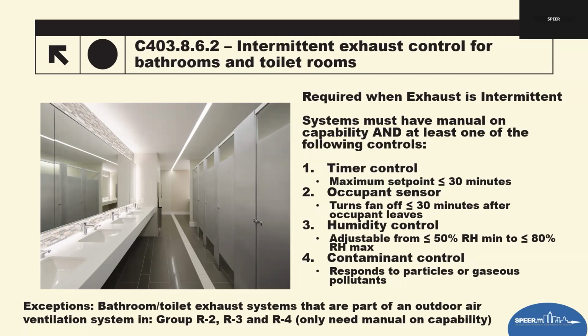And then if you have contaminant-based controls, these controls activate the fan in response to air quality triggers such as VOCs, parts per million, particles, CO2. The code now allows these systems to have alternate ways of basically ensuring proper ventilation when the space is occupied. There are exceptions, so are occupancy integrated systems. There's one important exception. So if the bath or toilet exhaust is part of the outdoor air ventilation system for multifamily or residential group type R2, R3, and R4 buildings, then only a manual on control is required. However, the code is clear that an offset point is not allowed to meet minimum requirements. So the system must still meet the ventilation design intent. So that means that still has to be tested.